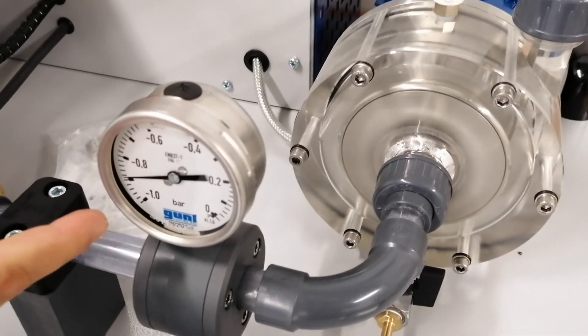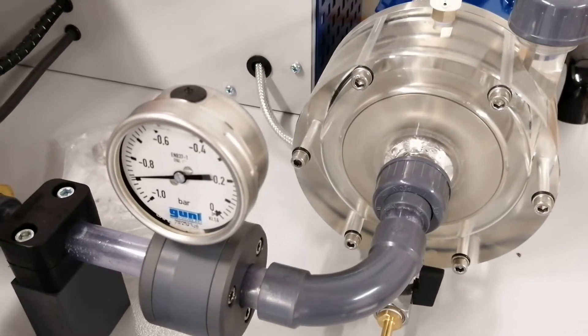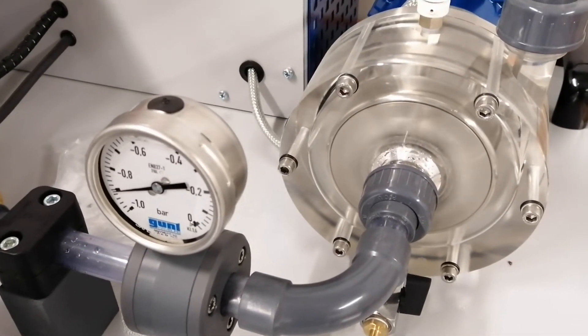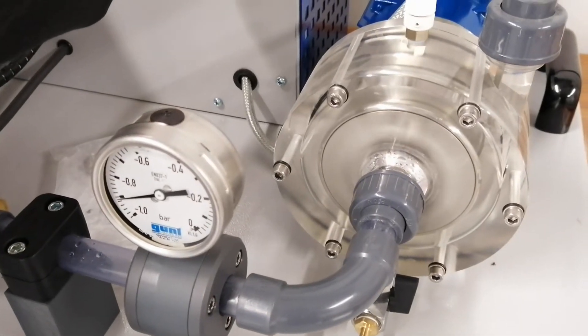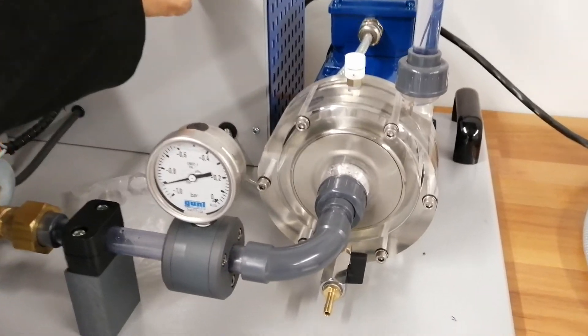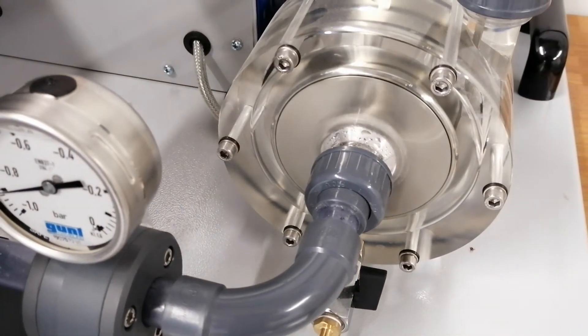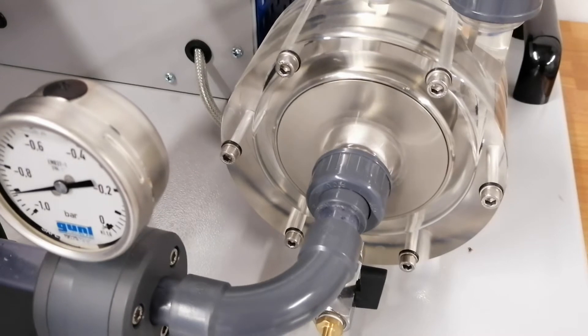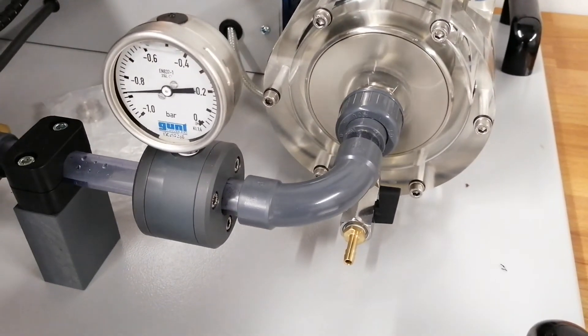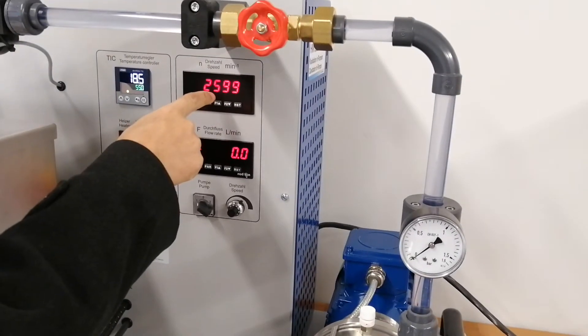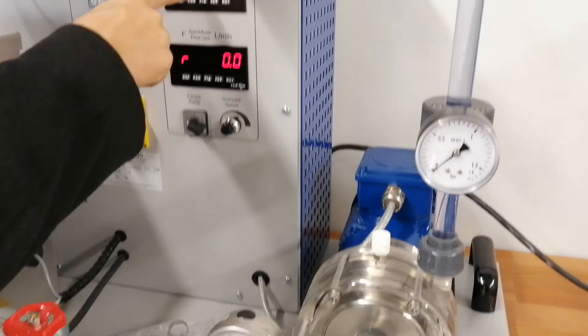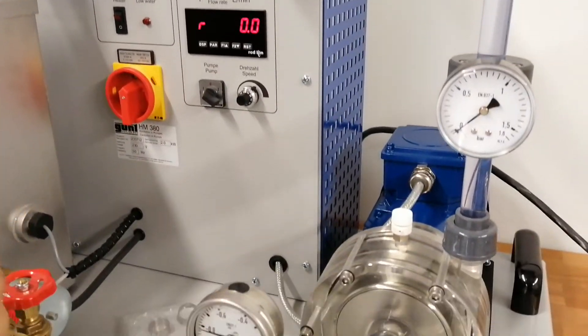Negative, maybe minimum. Now again, if you decrease pump speed, we can observe what happens. You see, by decreasing motor speed or pump speed, it is normal now. Yeah, you see the speed from 3400 to 2500. Then no problem.